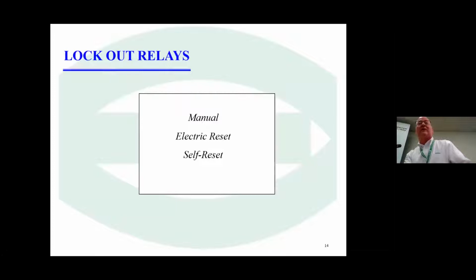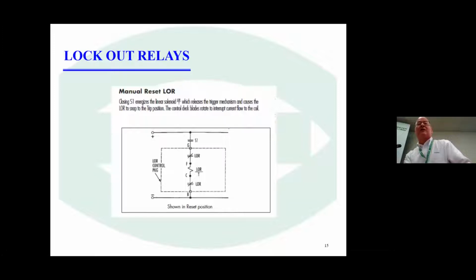Okay, so we talked about lockout relays. I demonstrated the manual and the electric reset. Just to go over a summary of the control circuit. In the manual reset lockout relay, my S1 contact at the top of that diagram is your system protection relay. So if you have a 50/51 overcurrent relay, or a bus differential 87 style protective relay for bus protection, or an 87T for a transformer system protection, that would be the output contact from that relay as your S1.